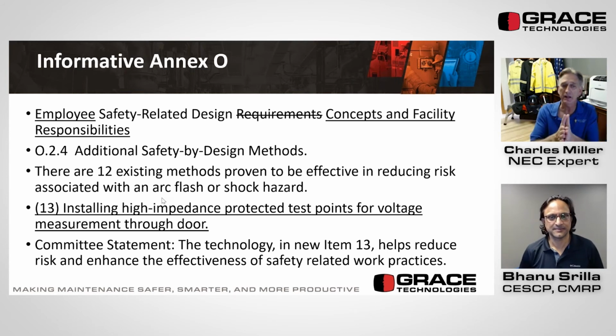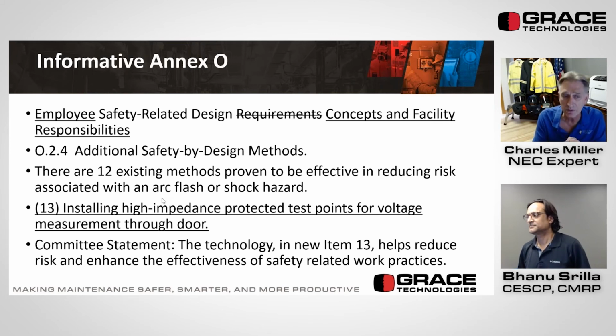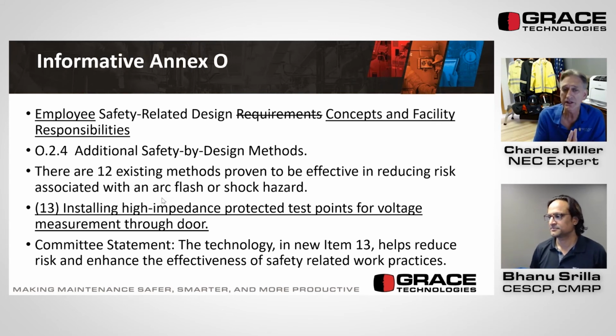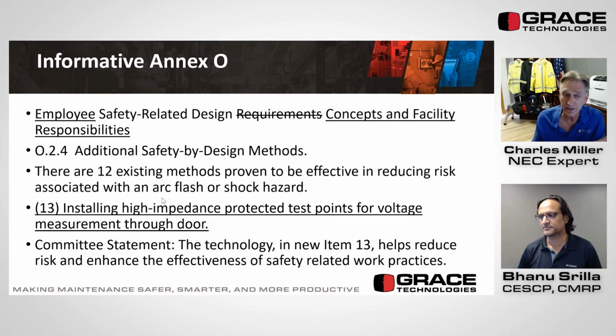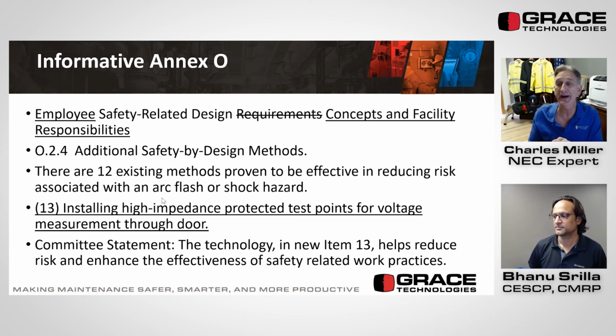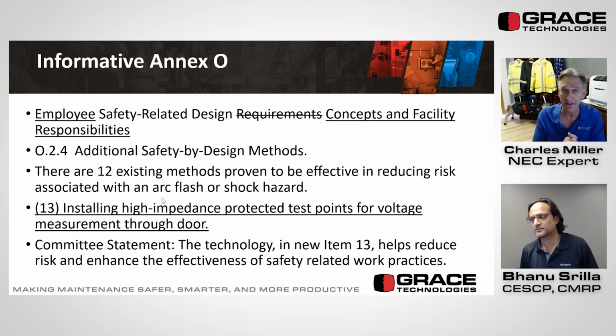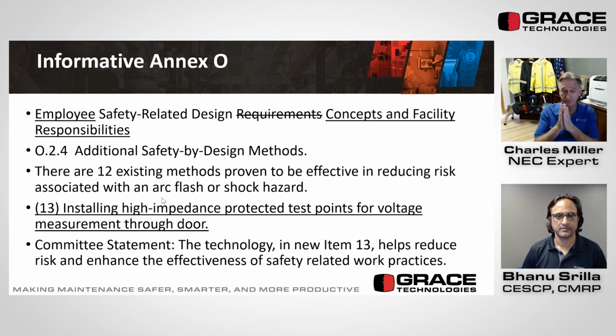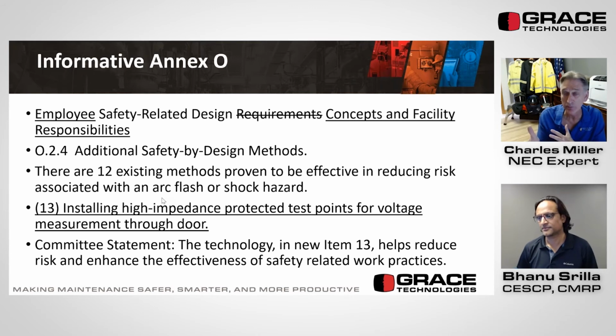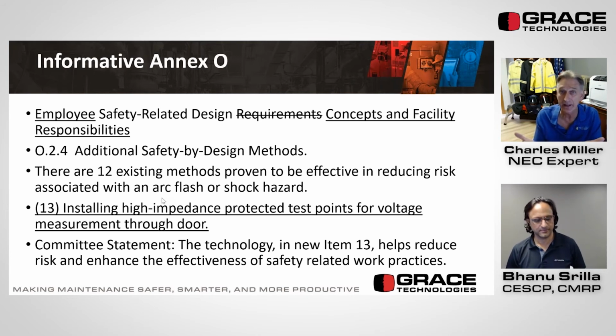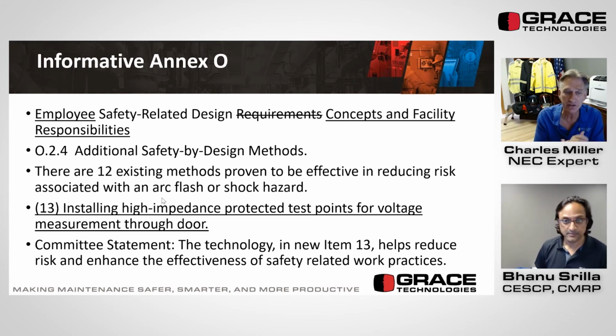In O.2.4, this is additional safety by design methods. There are 12 methods listed that have proven effective in reducing the risk associated with arc flash and shock. Here is an additional one that was added, which hopefully will stay and be in the next edition of 70E.